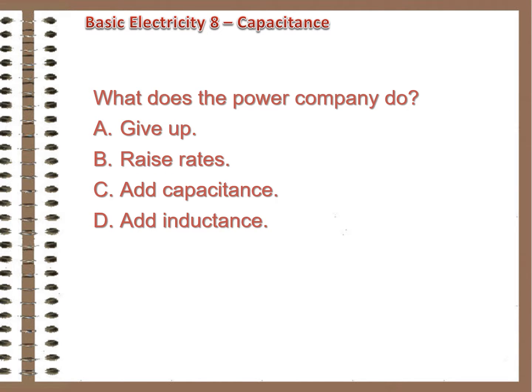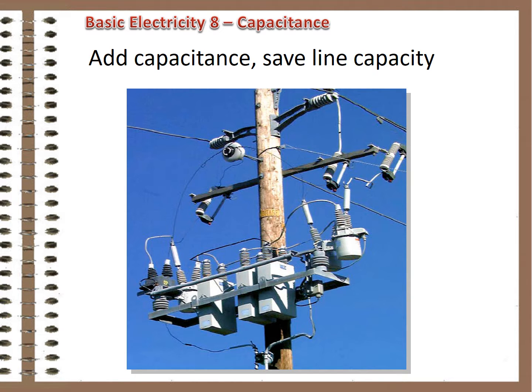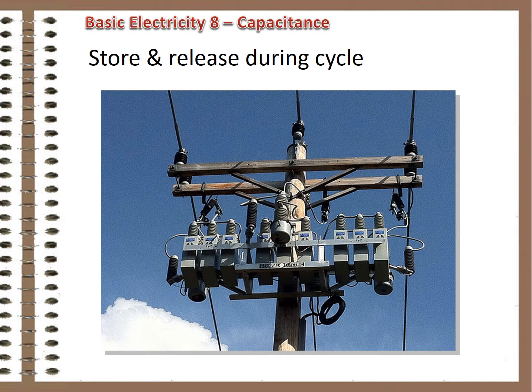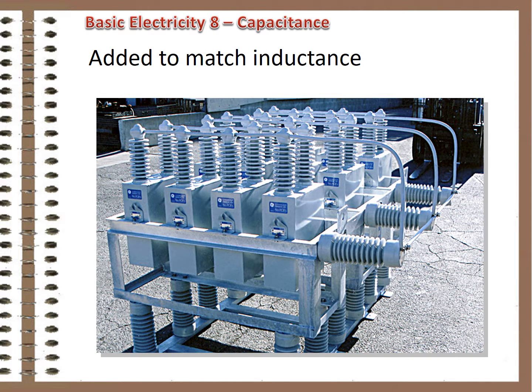The solution: if capacitance is added to the circuit near the source of inductance, the effect is cancelled locally and reactive power doesn't have to be transmitted through the lines, saving the capacity for watts. Each capacitor acts like a temporary battery, storing charge in part of the cycle and releasing it in another, causing a delay in the change of voltage. If planned and sized correctly, the delay in voltage change will match the delay in current change caused by local inductance, and the circuit will have a minimum of reactive power flow.